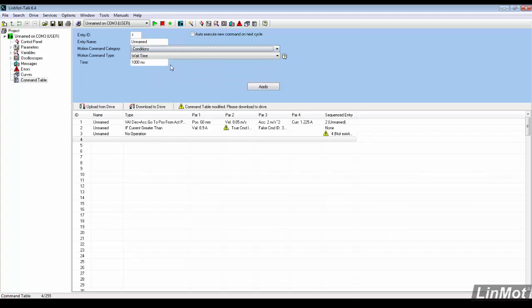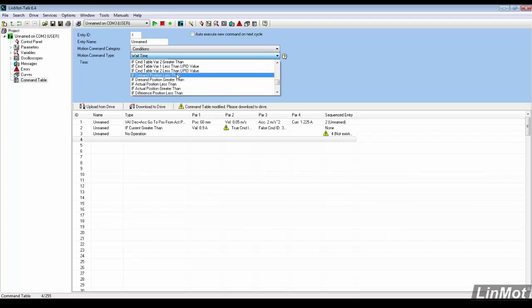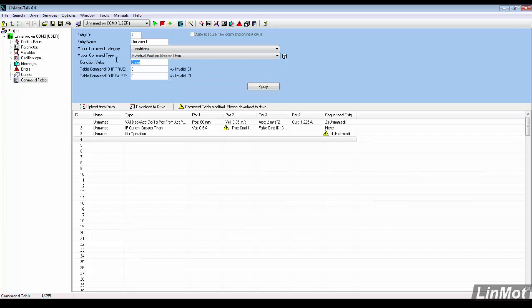Under conditions, look for the motion command if actual position greater than. The condition value will be set to 53mm. If the motor moves past 53mm, it will retract. If it does not, the current will be checked again.